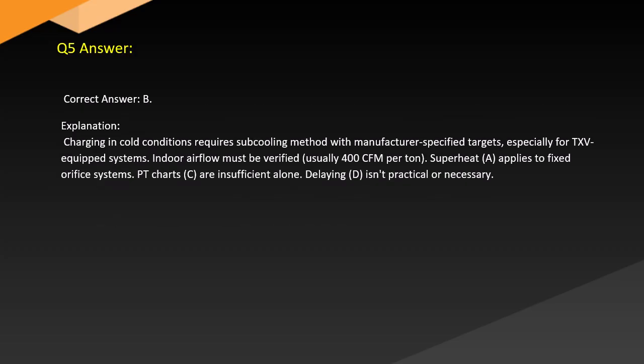Answer. Correct answer: B. Explanation. Charging in cold conditions requires the subcooling method with manufacturer-specified targets, especially for TXV-equipped systems. Indoor airflow must be verified, usually 400 CFM per ton. Superheat applies to fixed orifice systems. PT charts (C) are insufficient alone. Delaying (D) isn't practical or necessary.